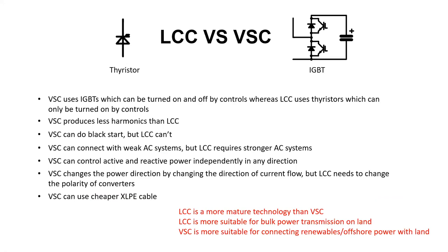VSC produces less harmonics than LCC. VSC can also do black start, but LCC can't, or LCC can, but with additional equipment, which once again has an impact on the layout. VSC can connect with a weak AC system and perform better when connected with a weak AC system, but LCC generally requires stronger AC systems to work efficiently with.